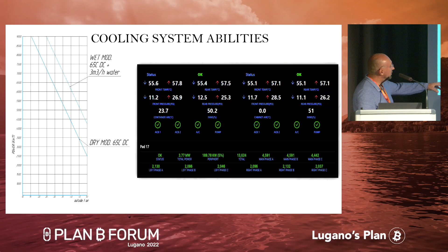This graph shows we can go up to 50 degrees ambient. Of course the cooling system's efficiency drops a bit, but this is a very rare condition even in the hottest regions on the planet. In that case we can simply reduce overclocking. But in most cases - 30, 35, 40 degrees - we're at a cooling capacity level of 6.5 megawatts for this container.